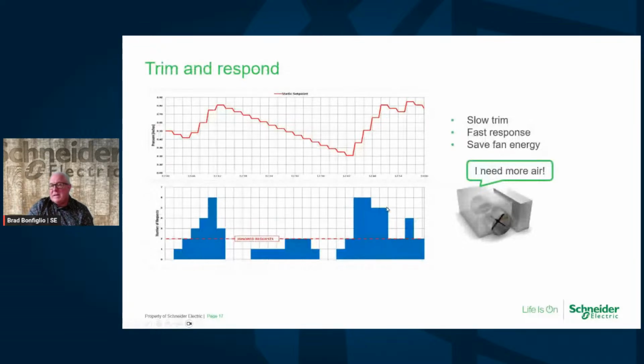And trim and response, by the way, is already mandated by Title 24 in California. So this just adds to the same thing that's already happening in the market. So typically on trim and response, and I'm going to give you this in layman's terms, you're going to look at every single terminal unit. And what normally you do is control static 2/3 of the way down the ductwork. Obviously that looks at all of them being equal, and I'm going to control off the 2/3 of the ductwork. So there's no real advantage to one box working differently than the other. It's looking at that one static point.